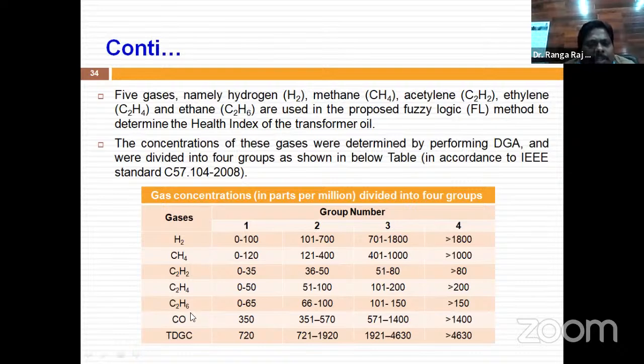So there are 5 to 6 inputs—gases—and the conditions are decided according to standard. One is a good, excellent condition: if the value of hydrogen is between 0 to 100, we consider that an excellent condition for hydrogen gas. Similarly, good, poor, worst—if the hydrogen value is greater than 1800, it is worst.